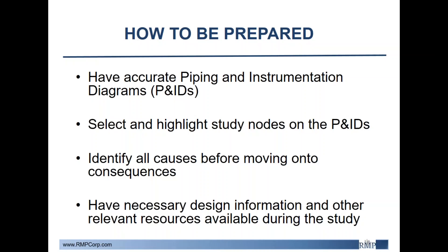Next is selecting and highlighting study nodes on the P&IDs, going along with the flow of the process as much as possible. Once everything is noted, the team can move on to identifying causes. It is best to address all causes throughout the node before moving on to consequences, safeguards, and risk ranking, because safeguards and consequences could appear in numerous places and you don't want the team to get sidetracked and miss causes. Finally, it is good to have additional design information available, such as set points of PSVs, alarms, shutdowns, and design parameters for equipment like maximum allowable working pressures.